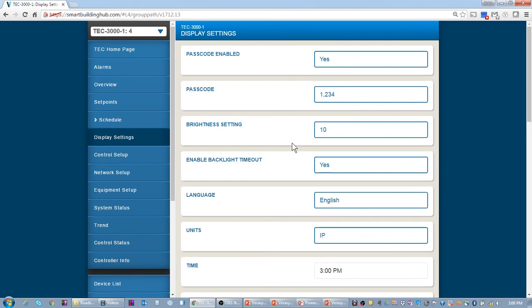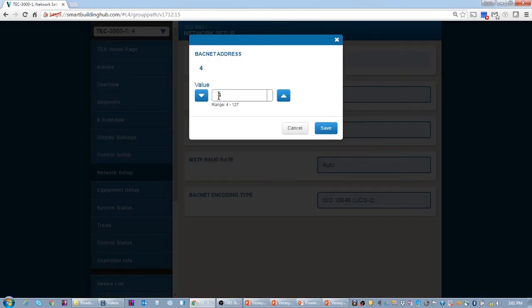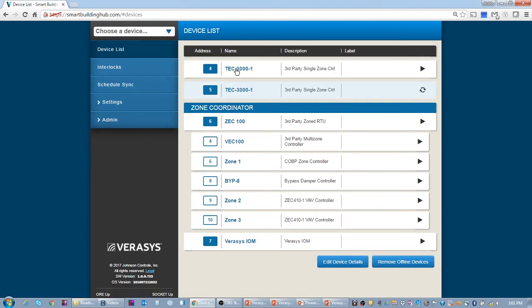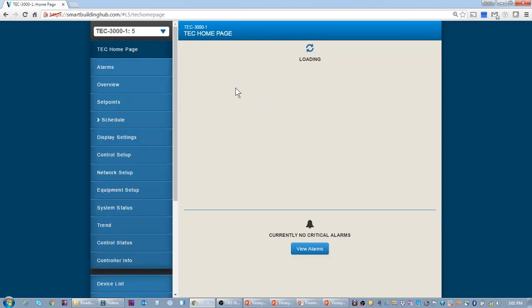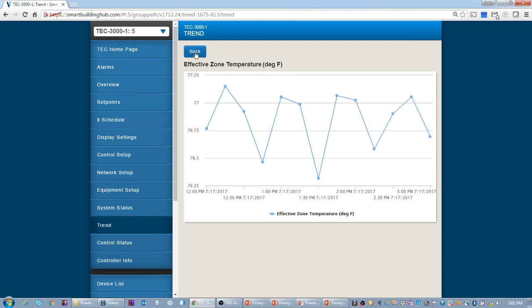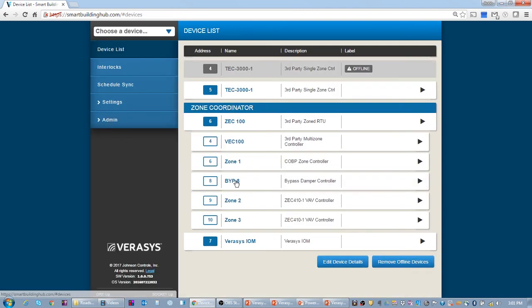The best way I can describe how it's different than a building automation system — remember having to define all those objects at a particular address? Well, let's just change the address. I'm going to switch it from 4 to 5. If I go back to my device list, I just told it to go from 4, and now it's going to 5 — you can see that 5 popped up, and the old one will go offline. I can click back in here, and notice when I go to my trends, that's the same trend I just showed you on address 4. All of this definition is the same. In fact, every time you take this model of TEC and hook it to the trunk, you're going to see the same parameters, same location — everything's the same. That's what smart equipment is doing for us.